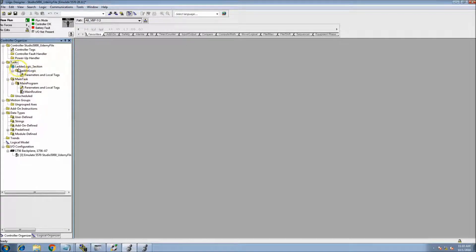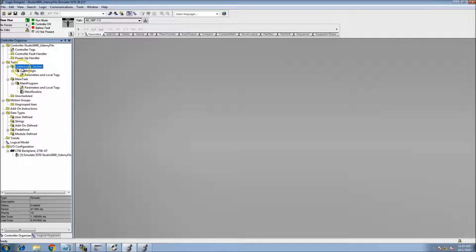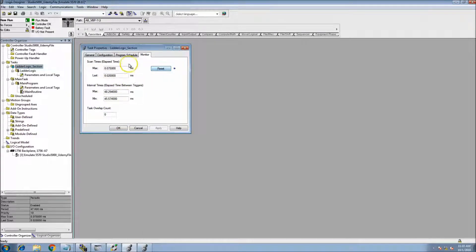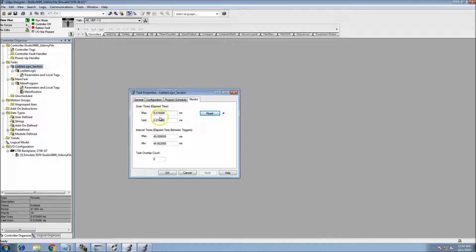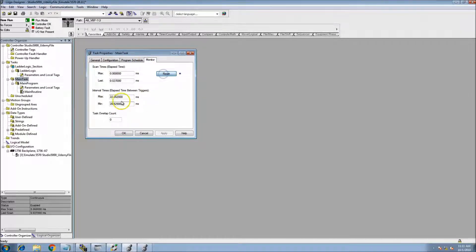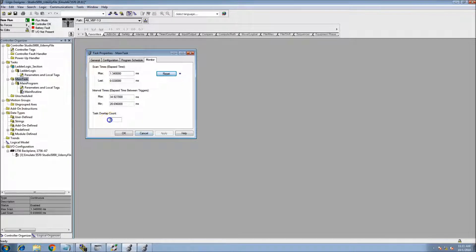There's really no difference between continuous and periodic besides the scan rate. If you look at the periodic task monitor, it shows the max time, the last time, and the intervals between when it started scanning — currently 47 milliseconds, with a minimum of 45. In the continuous task monitor, it shows minimum and maximum scan times and intervals, and whether any overlaps happened. We want to avoid overlaps.